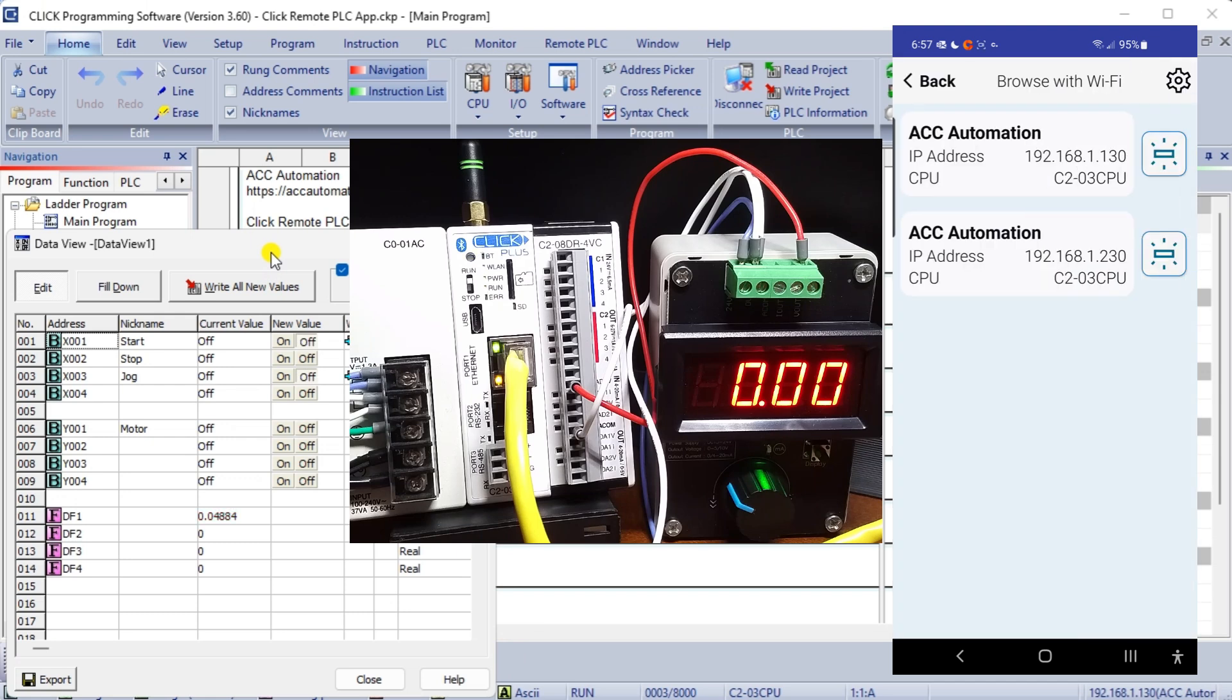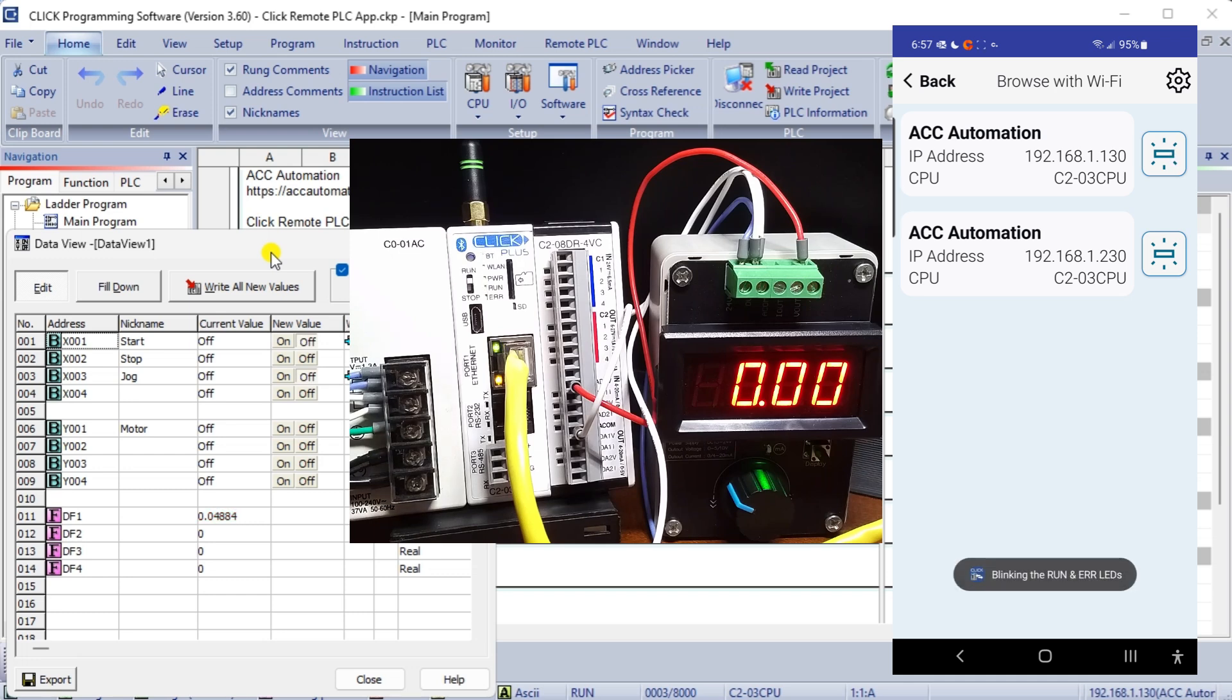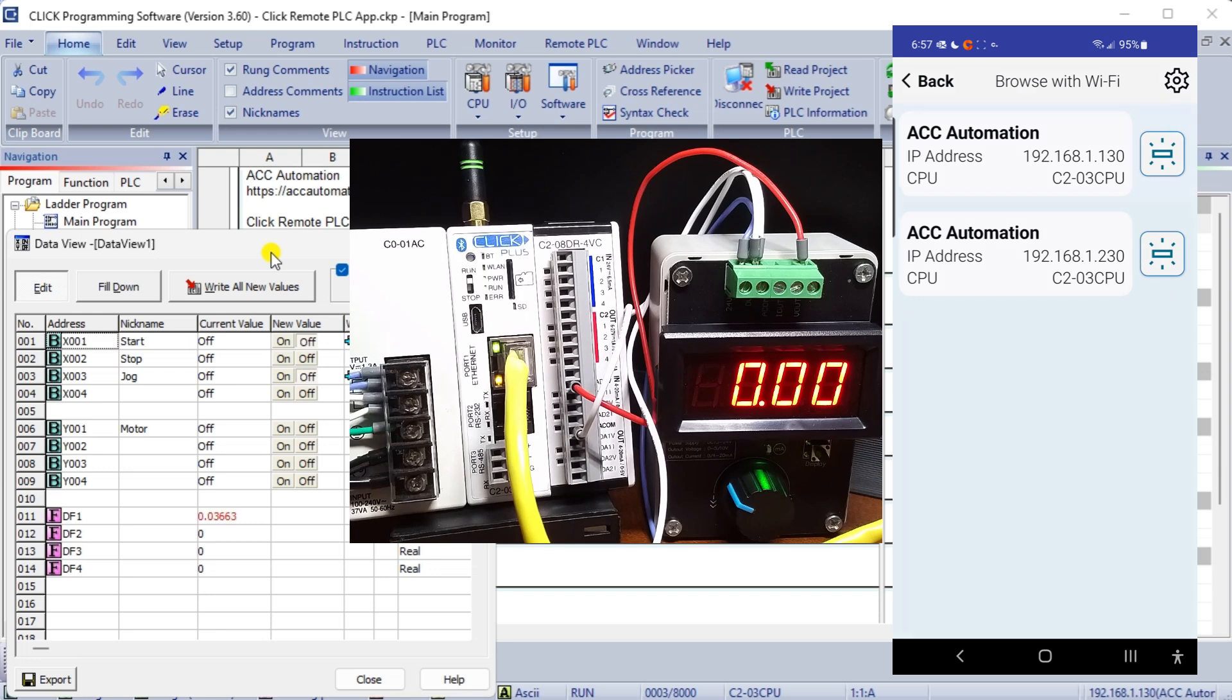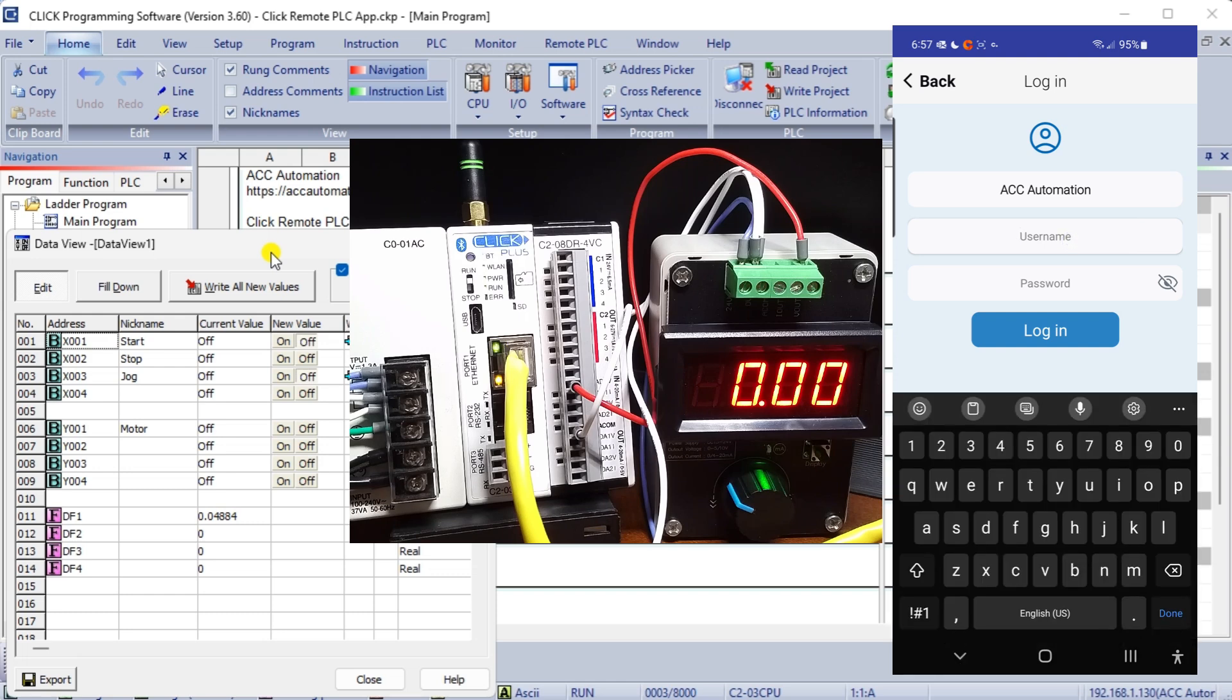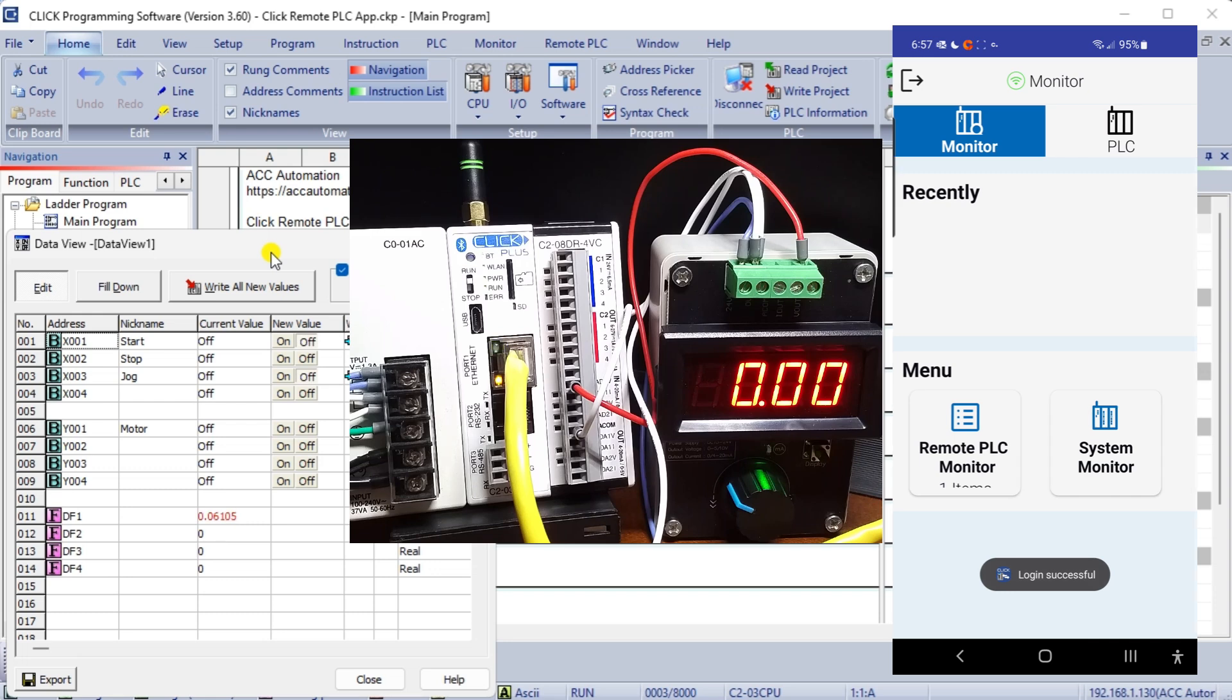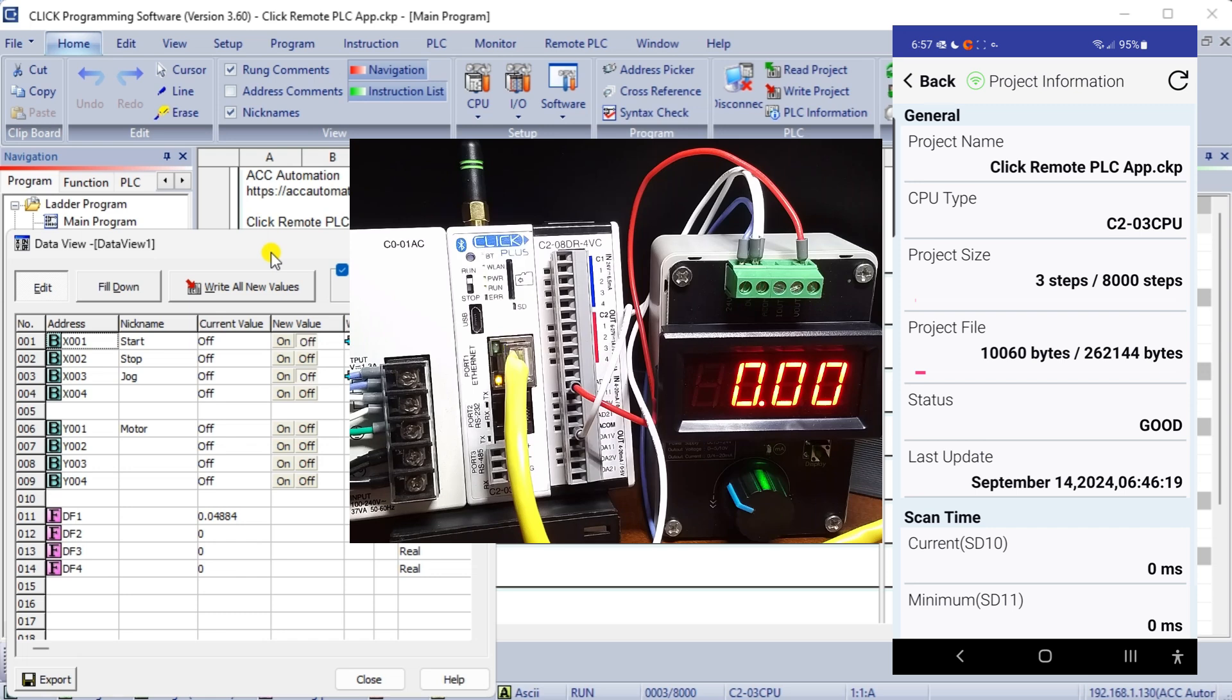On our Android device, call up the installed remote PLC application. Select the Wi-Fi connection. You will see two options, one for our Wi-Fi connection and one through our Ethernet port 1 connection. The symbol next to the connection will blink the light so we know which PLC we are monitoring or controlling. Select the connection you want to use on your Android device. You will now be prompted for your username and password. In our case, this is admin and 1234. Select login. We can now select monitor or PLC to view the information in the connected CLICK PLC controller.